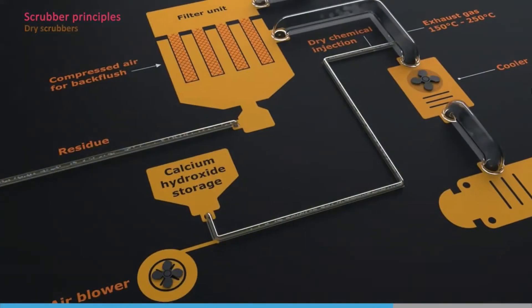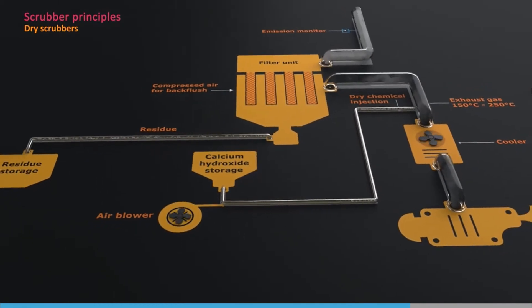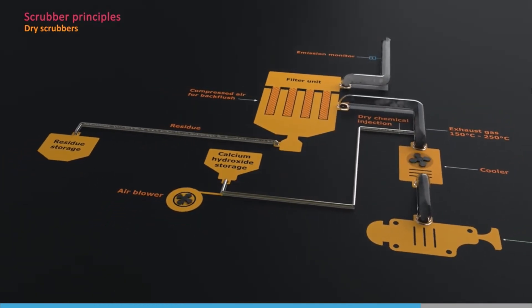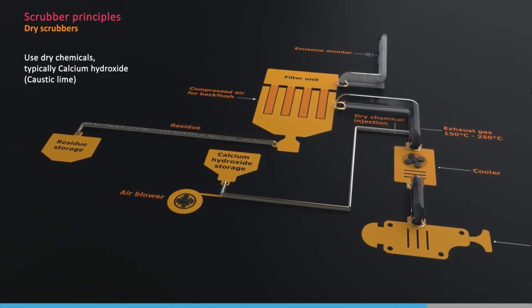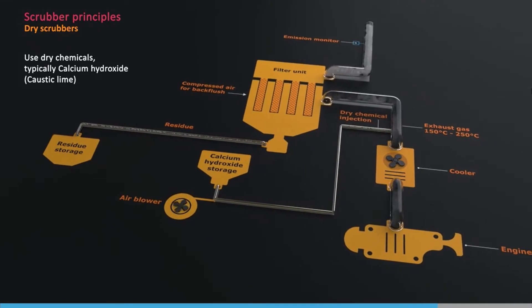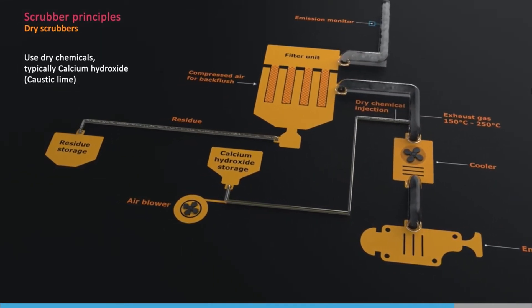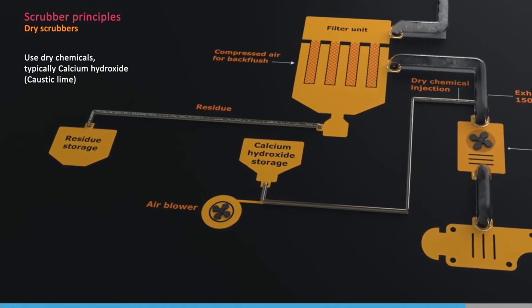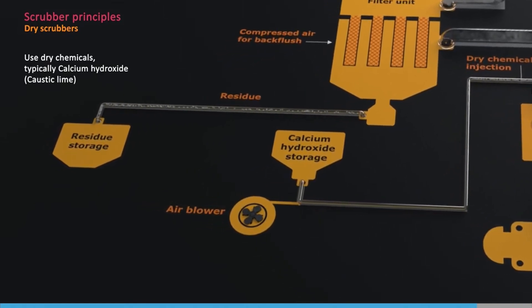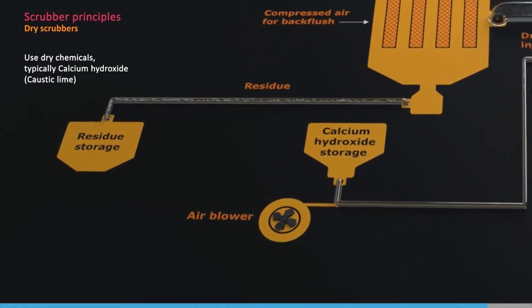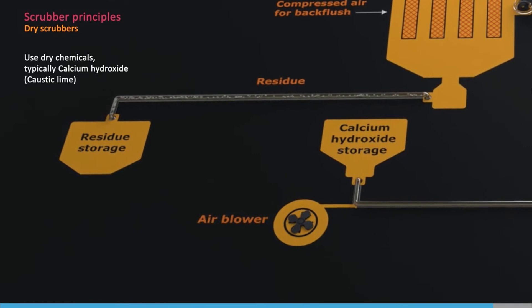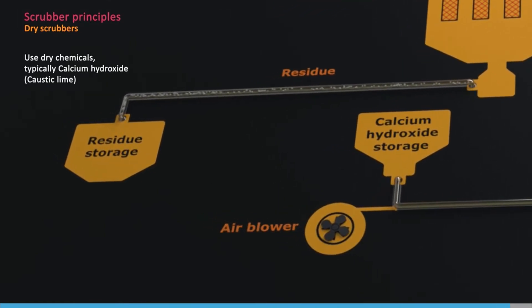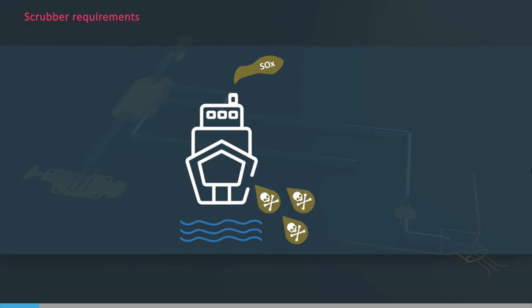Dry scrubbers, as the name suggests, do not use liquids. The exhaust gas is cleaned with dry chemicals, typically calcium hydroxide, commonly known as caustic lime. The dry chemical and waste products need to be handled and stored on board, and the waste products need to be discharged to shore reception facilities. They can reduce the sulphur emissions from exhaust gas, whilst at the same time keeping potentially harmful discharges into the sea within set limits.